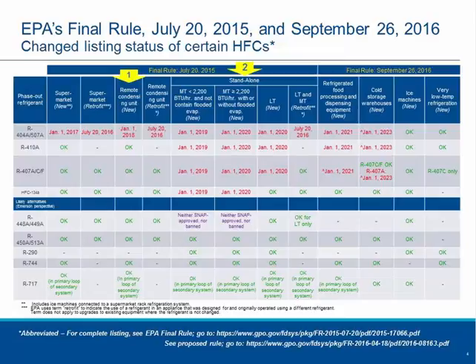This poses significant challenges for our industry, not only in terms of timing, but also the choices of refrigerants that are in fact available. For this audience, let me mention that R404A and 134A are characterized as A1 refrigerants. These are non-flammable refrigerants. And the whole point of the EPA in delisting these refrigerants has to do with what we call the global warming potential, the GWP. There's a national as well as international phase-down agreement to get this done, and in doing so, it's putting pressure on us, especially on new pieces of equipment where these delistings are going to occur. So we've had an understanding that these are A1s, non-flammable refrigerants. The question now becomes for equipment manufacturers what refrigerants they are going to go to.